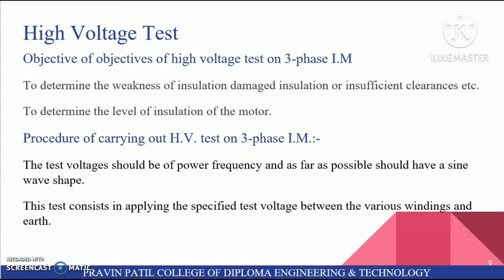Next is high voltage test. So objectives of high voltage test on 3-phase induction motor are to determine the weakness of insulation, damaged insulation or insufficient clearances, etc. To determine the level of insulation of the motor.